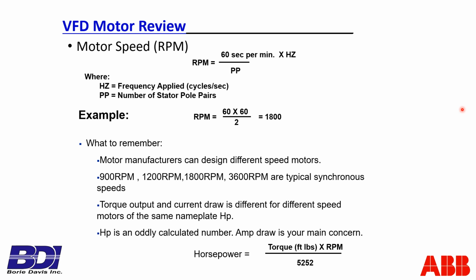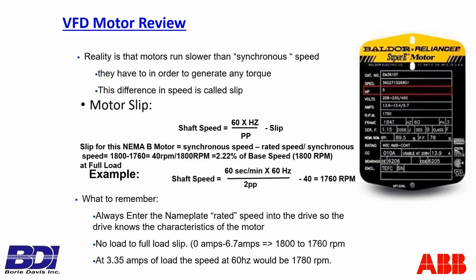And we talked about those are typical synchronous speeds, but we don't drive synchronous motors. We drive induction motors. But there's the equation. Torque in pound-feet times RPM divided by 5250 would equal the horsepower. The rate of doing work would be the rate of the length over time and the load. Reality is an induction motor, by its principle of induced voltage, does not operate at synchronous speed. There is a difference between the rotor speed and the stator rotating field, which comes from the drive. That difference is called slip, motor slip.